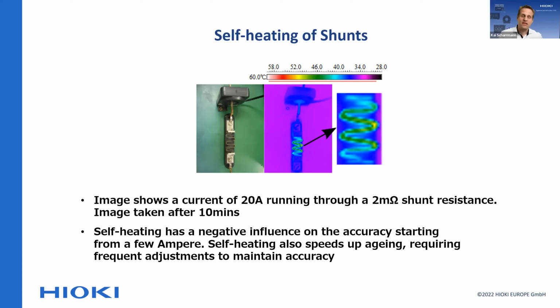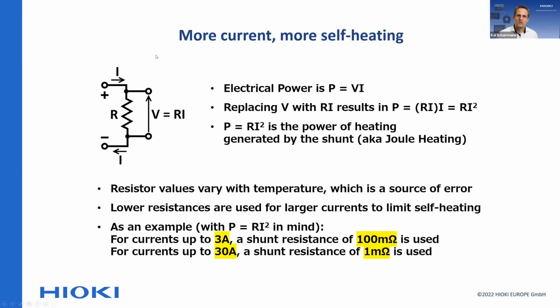One of the big things that you also have with these kinds of shunts, especially manganin shunts, is that driving high currents over them speeds up aging, and it requires frequent adjustment to maintain the accuracy. Sometimes you can see with shunts, when there is an instrument that has been adjusted, that only 3 months of accuracy is guaranteed or something like that. So more current, more self-heating, that's normal.